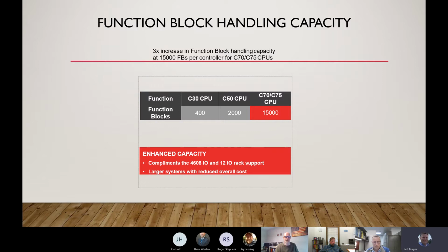The hardware that you have in the HC900 can accommodate over 4,608 I/O and up to 12 I/O racks. We talked about the remote I/O racks or additional I/O racks on a CPU. You can do up to 12 off of the one CPU. For larger systems, this will help reduce the overall cost.